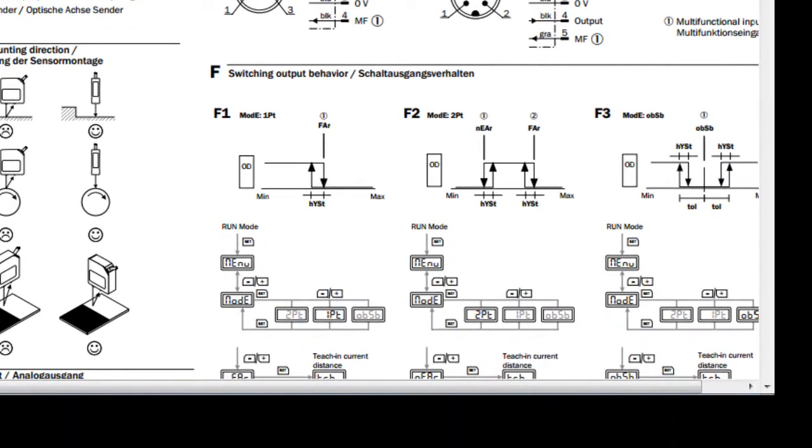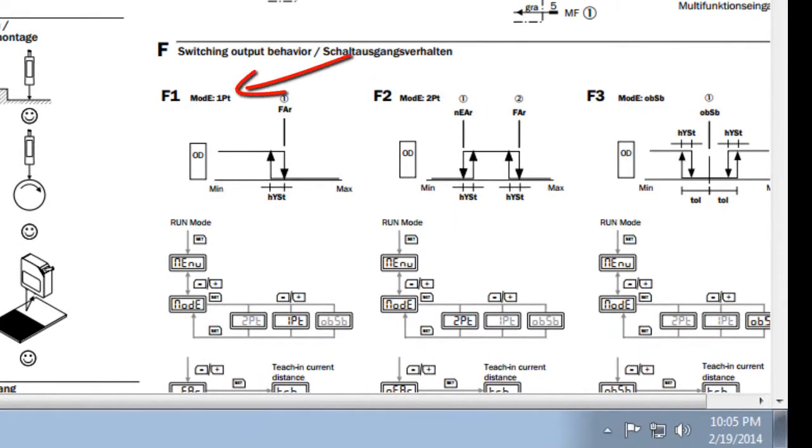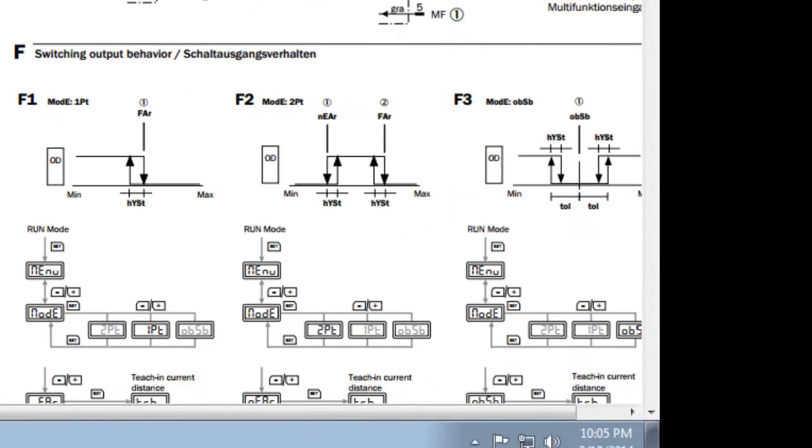So we have a couple different modes we can do our switching output. We have mode for one point teach. So you just want to know if something is at a certain distance or closer. Give me an output. The other one will be a two point teach. That's a window mode. So you have a near and a far that you need to teach. And then there's a third mode called this OBSB mode. That is object between sensor and background is what the acronym is. And we'll actually handle that in a separate video on advanced functions.